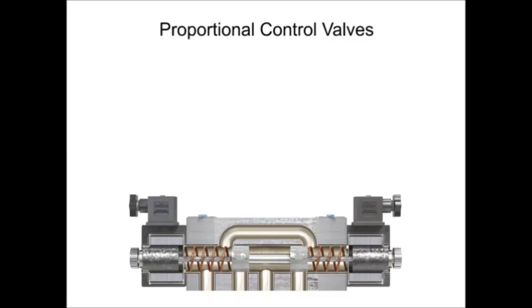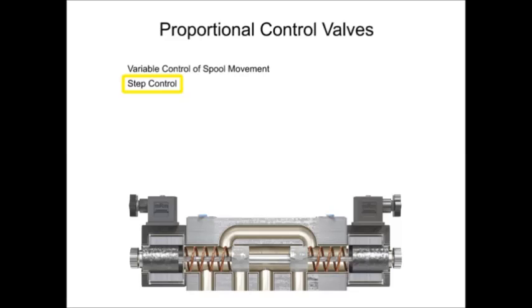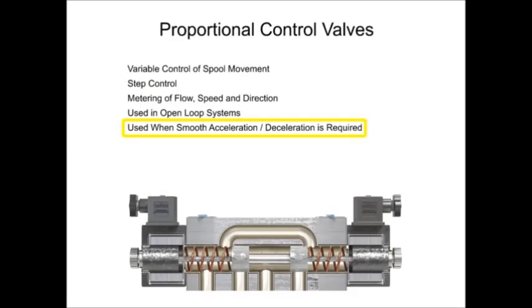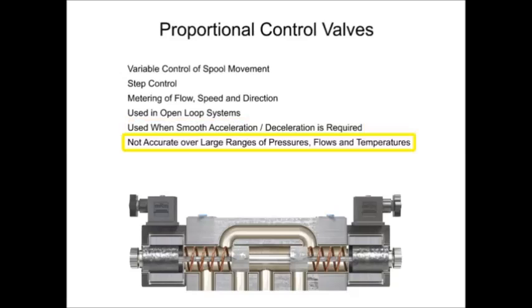Proportional control valves allow for variable control of spool movement, which allows more step control and metering of flow, speed, and direction. Most valves of this design are used in open-loop systems to smoothly accelerate and/or decelerate an actuator or cylinder. The proportional control valve allows for a simpler hydraulic circuit, but it is not accurate over a broad range of pressures, flows, and temperatures, and neither are they highly responsive. Proportional valves offer a variety of machine cycles which can safely be operated at greater speeds, resulting in improved machine cycle times and production rates.